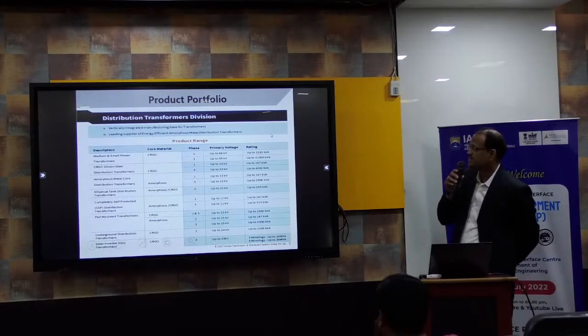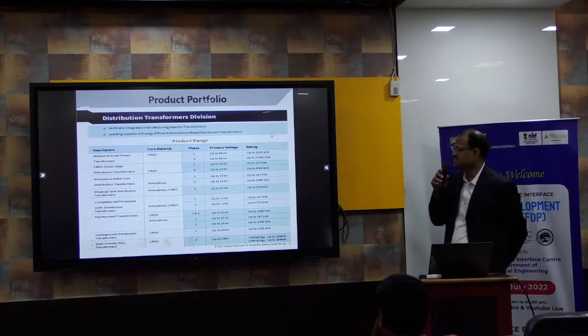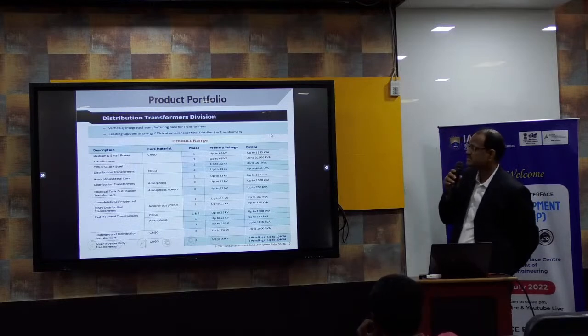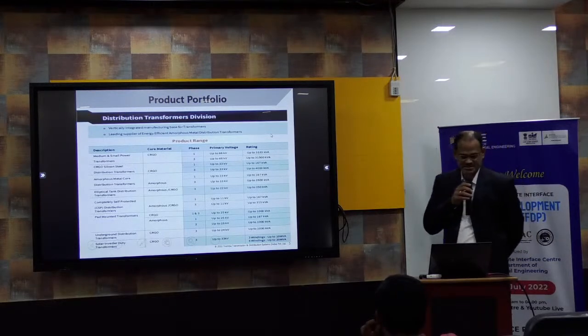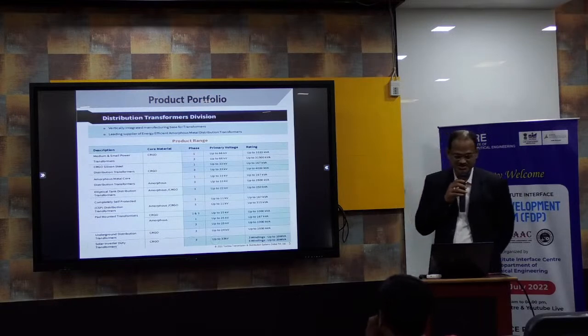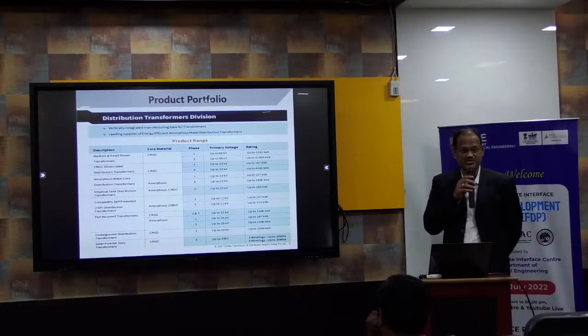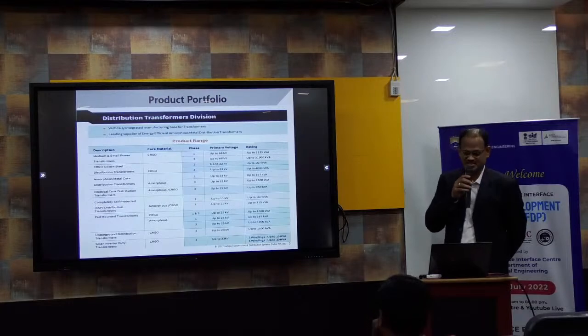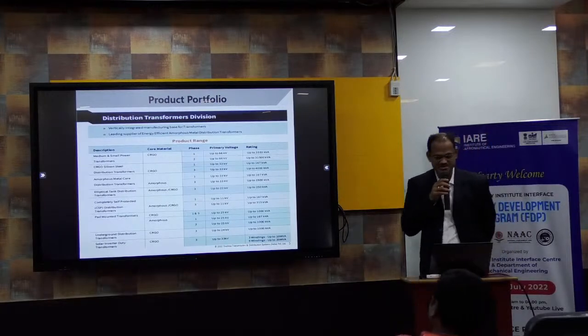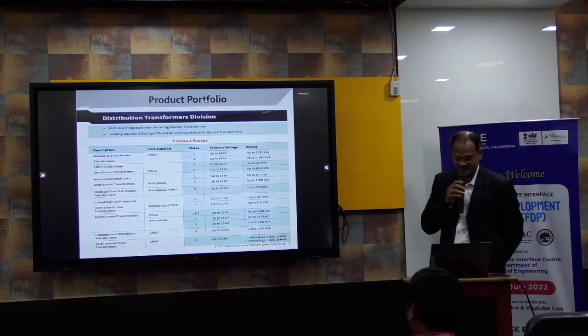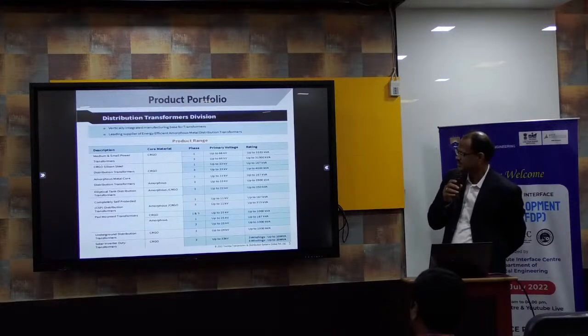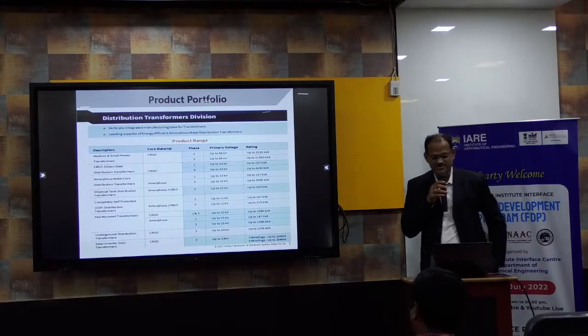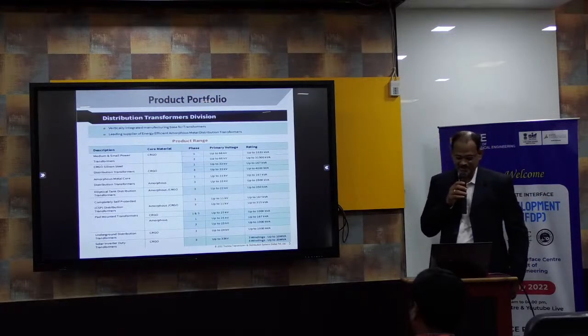It is a vertically integrated manufacturing base of transformers and a leading supplier of energy efficient amorphous metal distribution transformers. The product range: medium and small power transformers of CRGO. CRGO means cold rolled grain oriented, one kind of material we are using in the transformer. That type, the 3-phase and single phase variety, is there, up to 66 kV voltage class. For single phase, 33 rating, up to 3 phase 31.5 MVA, call it 31500 kVA.